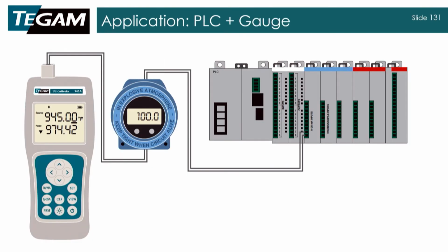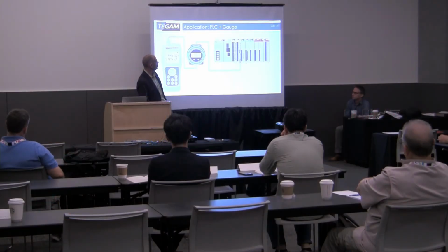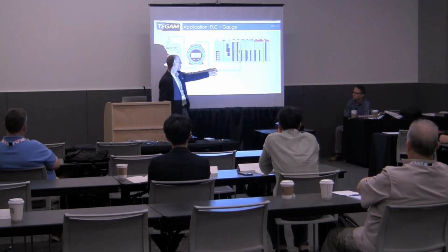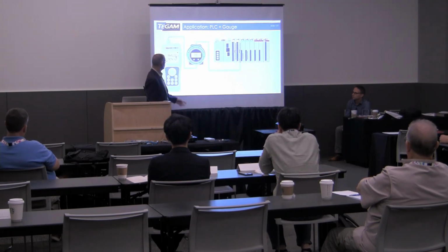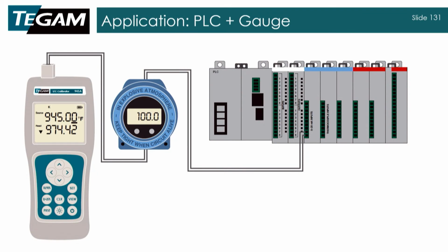This next slide I put in here just to talk about intrinsically safe a little bit. People do this all the time. You've got an intrinsically safe transducer here, and then you've got a 4 to 20 milliamp loop. But in this application, this is actually a no-no, because this calibrator is not intrinsically safe. You'd really need to have an intrinsically safe one to have it connected to this device, or this has to be kept completely out of the intrinsically safe area, and you have to run cable in or something.